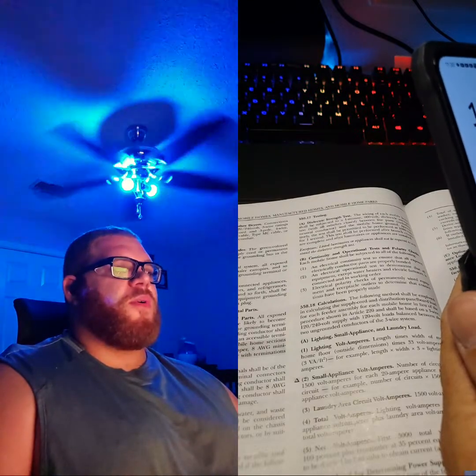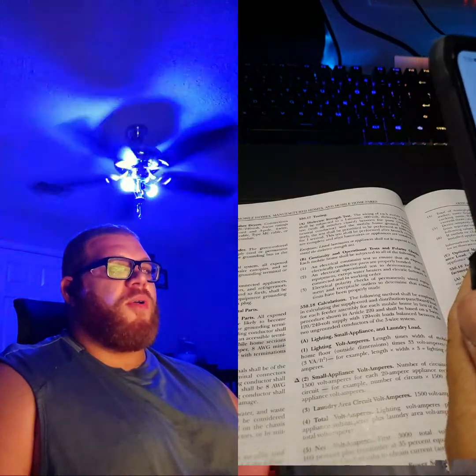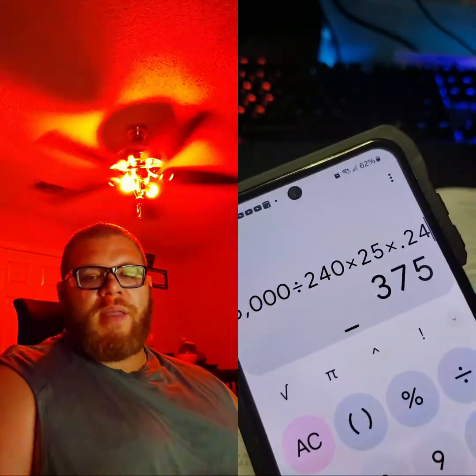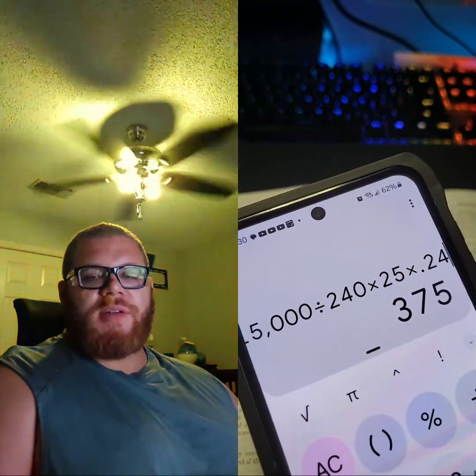So this is for the whole park. There we go. I did it this time. Times 0.24 is 375. Is this for the whole park? Yeah. And then you round up to 400. So you're feeding 25 mobile homes with that. Yep. And then when it freezes and they all turn on their ovens, you get rolling blackouts. Well, that'd be the best case scenario.